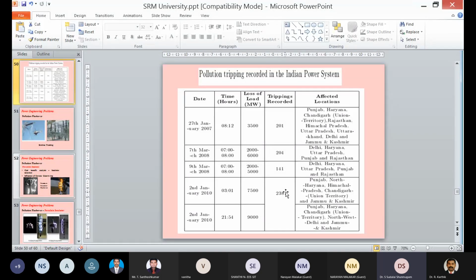So what happened is the government formed a committee in 2007, the Central Electricity Authority. They asked what is happening. Why, after defining and designing as per IEC 60071, are these trippings happening? Then we came to know that there is an additional phenomenon called pollution. Though we designed the line traditionally with respect to BIL, basic insulation level, now we also consider pollution withstand level when the system voltage is more than 220 kV.